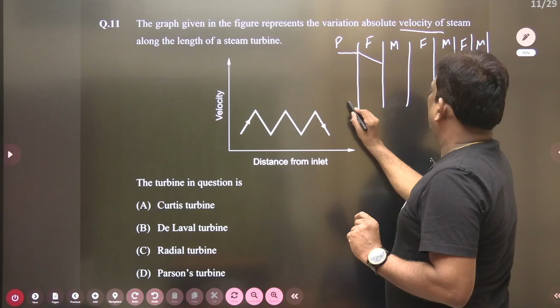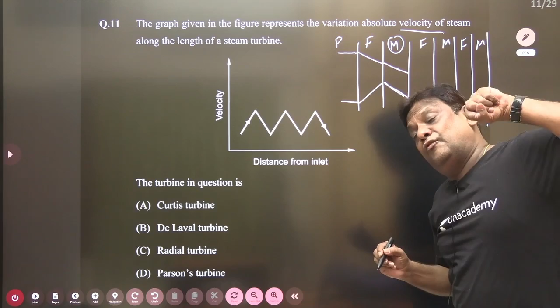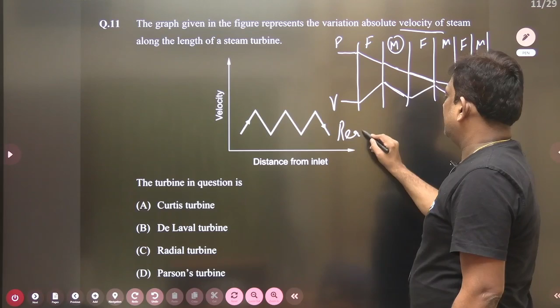In moving blades, again the pressure decreases. In moving blades, the velocity decreases. That's why I told you, in reaction turbines, in moving blades, both pressure and velocity, absolute. I explained very clearly in case of reaction turbines why the relative velocity increases in moving blades. All these I had explained, but he is talking about absolute velocity. The absolute velocity decreases and the pressure decreases, and both are responsible for developing power. That's why they are efficient. And again in fixed blades the pressure decreases, and in fixed blades the velocity increases. Moving blades both decrease. So if you see, this is coming out to be a reaction turbine.